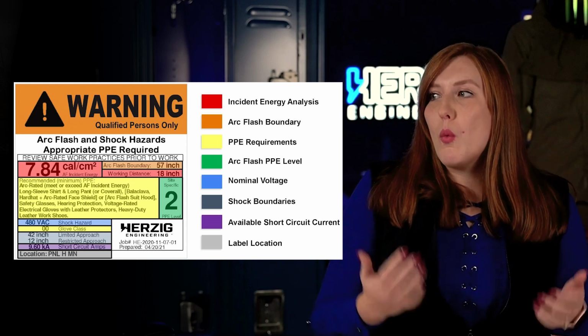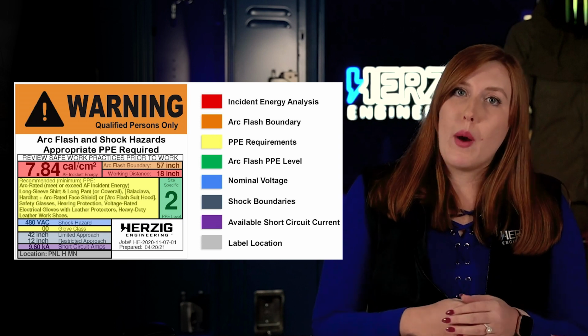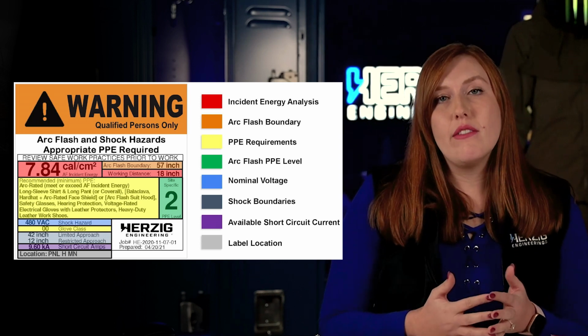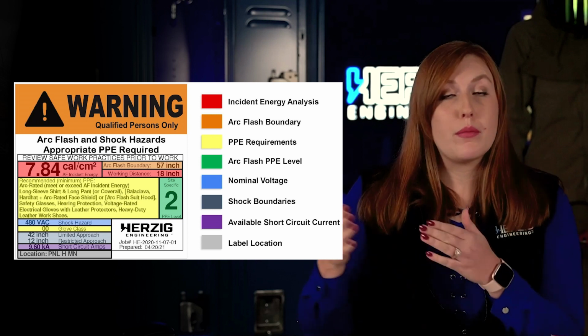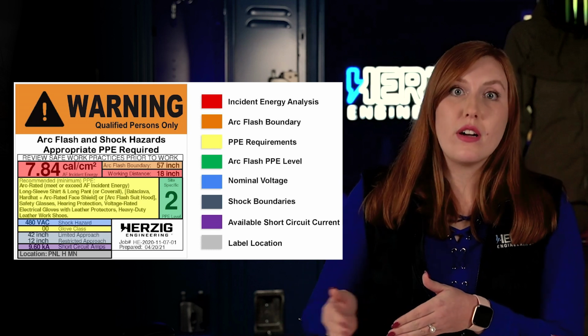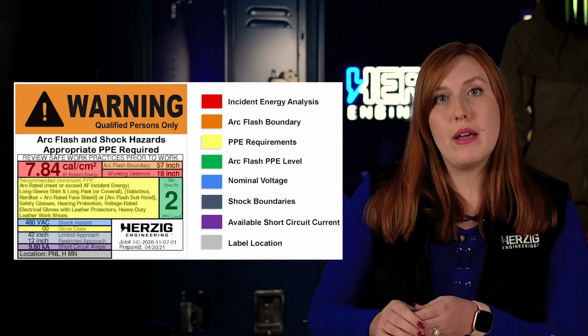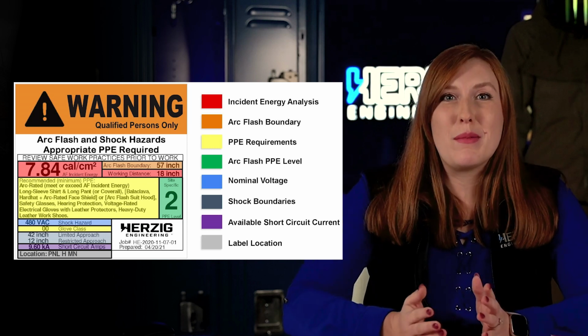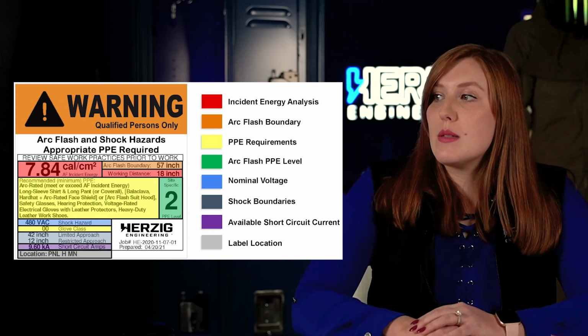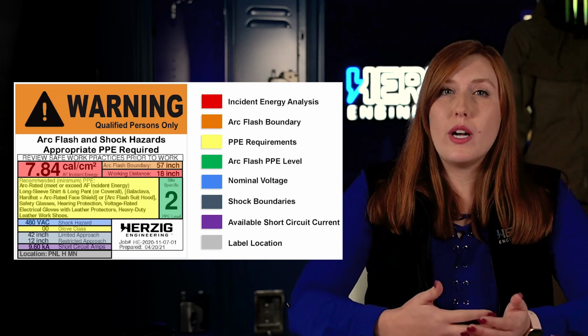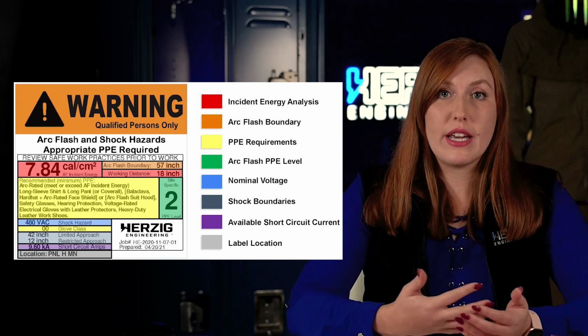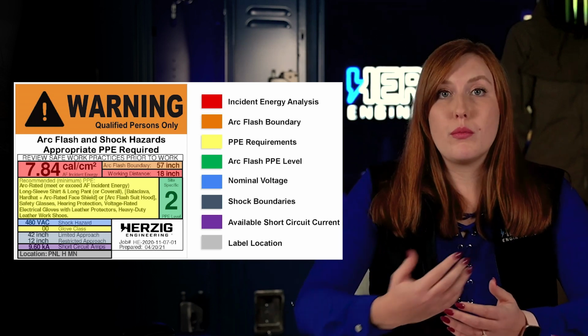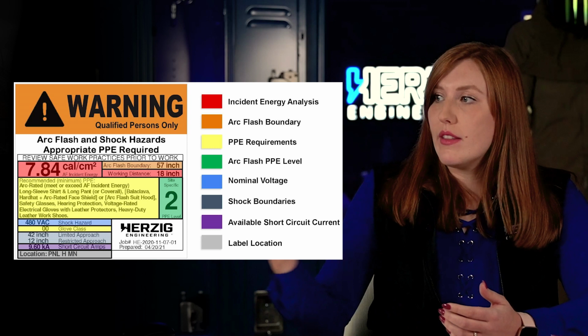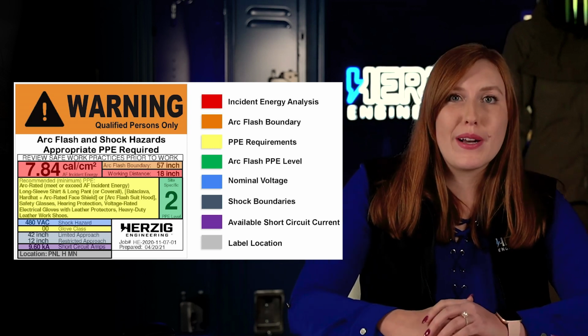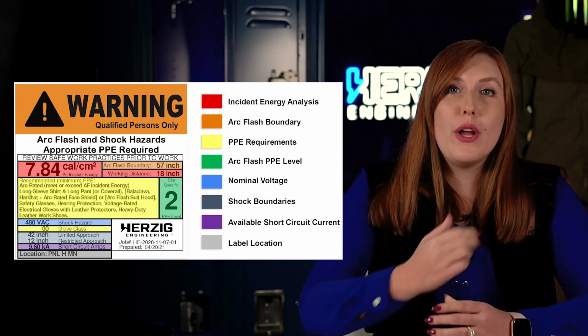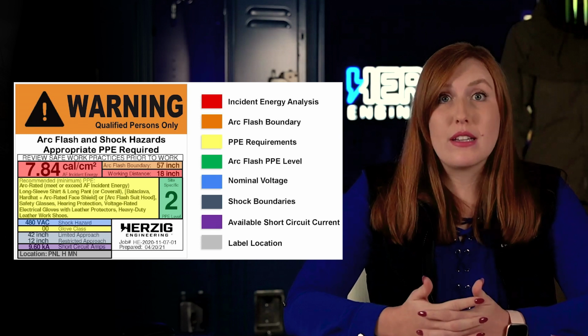What we do is we label out the specific PPE requirements. So we list out, okay, for this high of an arc flash hazard, these are the items of clothing or protective gear that you need to wear in order to protect yourself. If this arc flash were to occur and you're wearing this equipment, you will probably be pretty scared, but at least be able to walk away from it. We also put a site-specific PPE level, and this is going to mirror what PPE suppliers most of the time mark their gear as. For example, a shirt and pant that says a big old 2 on the sleeve and the pocket, well, that's considered okay for up to 8 calories per centimeter squared of incident energy. So if you know what your PPE says, it makes it a little bit easier to pick the right items.